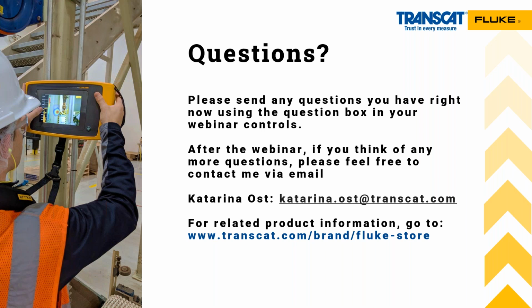Does installing an IR window void the UL listing on equipment rated less than 1000 volts? No. We have quite a few ratings on our infrared windows, including all the way up to the nuclear power rating for use in a nuclear power plant, which considers literally everything, including vibration and earthquakes. So no, it does not. We have a UL letter that says it does not derate the panel face, and actually the warranty of the window is the life of the gear itself.